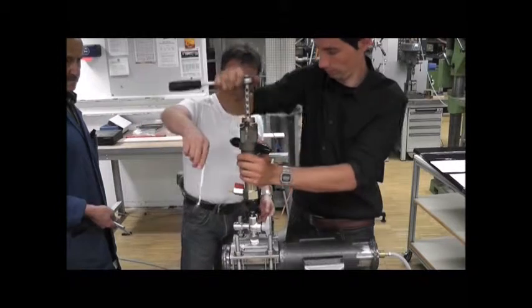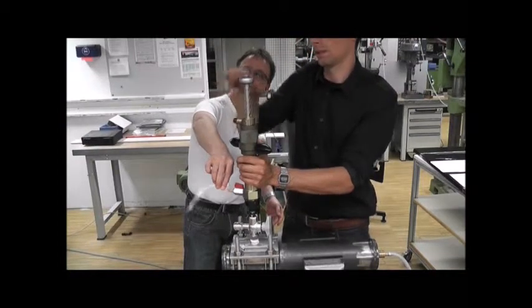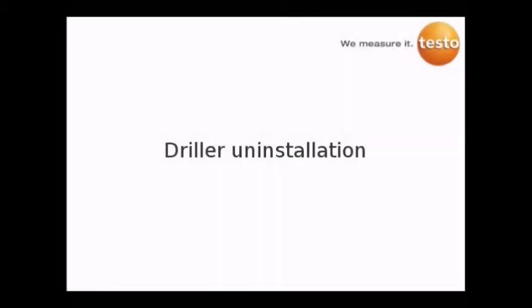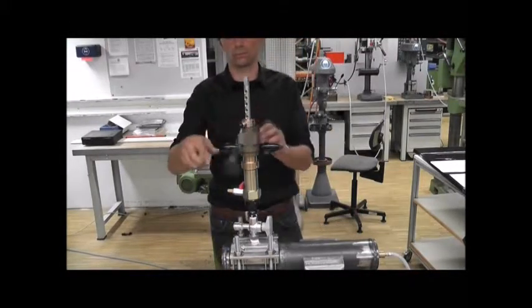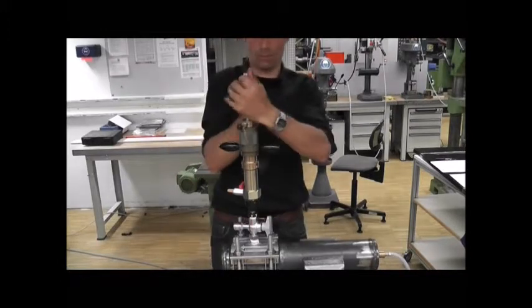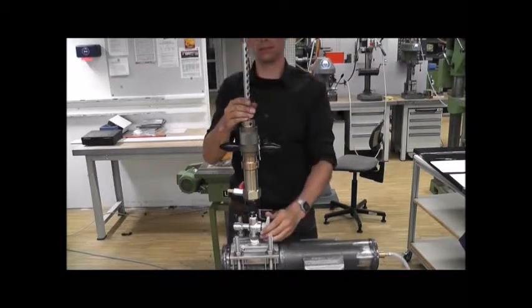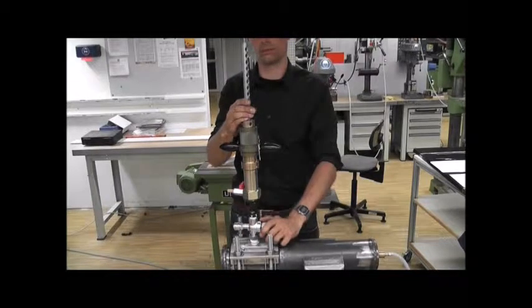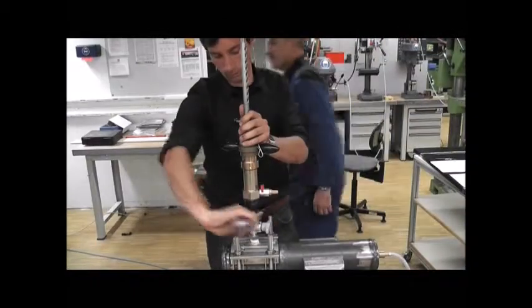If you are through the pipe, you will hear the compressed air out of the valve on the driller. Continue with the drilling till the volume is not growing anymore. Before you start to uninstall the driller, please prove that all screws are tightened. Now we have to uninstall the bolt. At this point the driller can kick back till the backstop. Keep your body away from this area. If the driller isn't coming out by itself, try with shaking and rotating to force the recoil of the driller. If the driller is on its endpoint, close the ball valve.